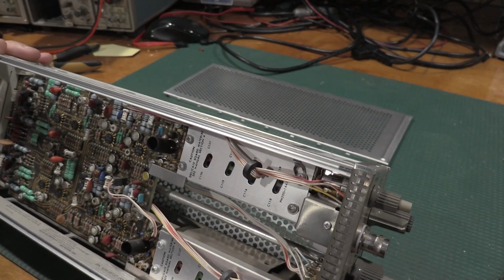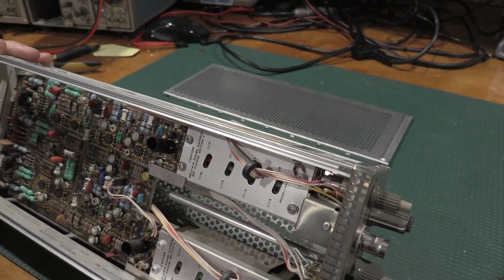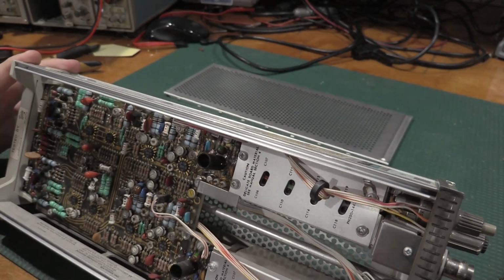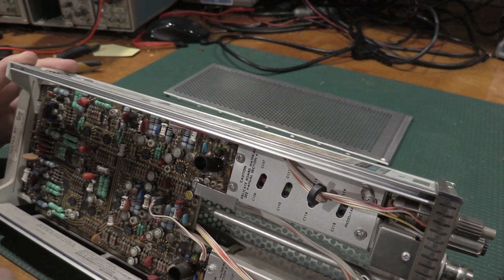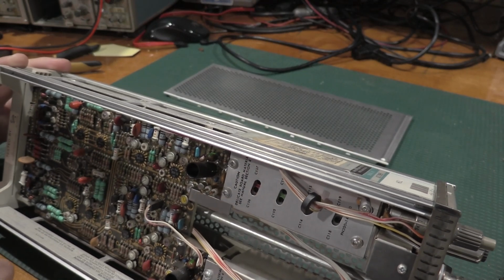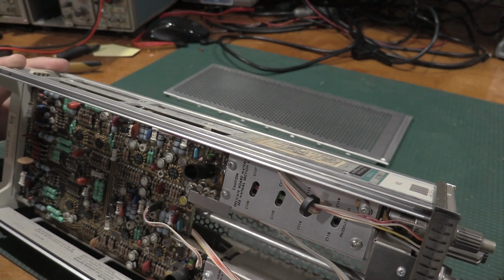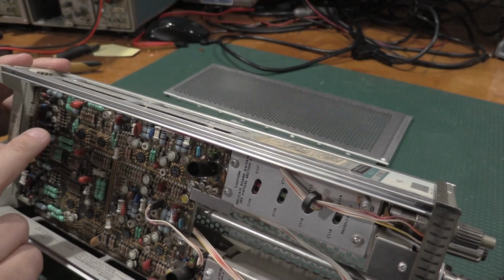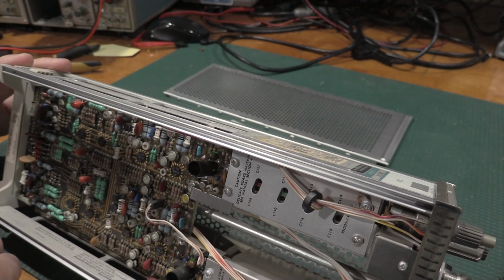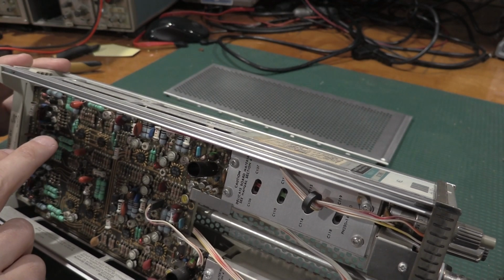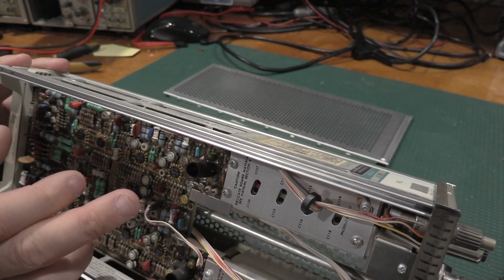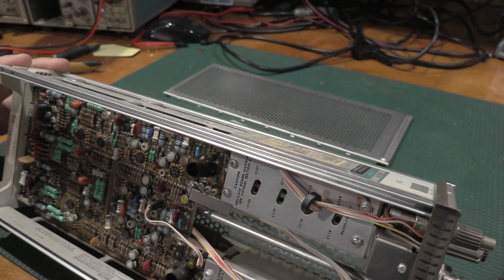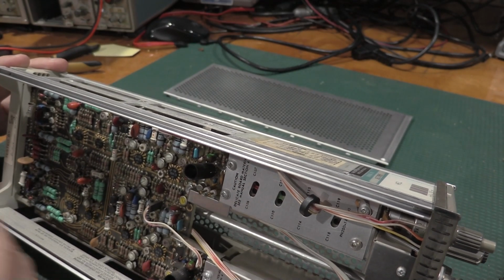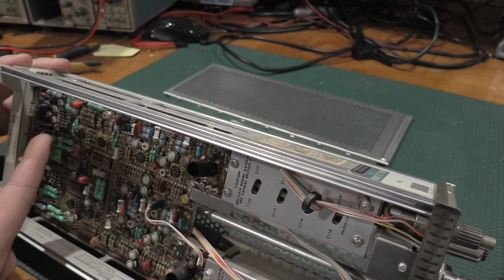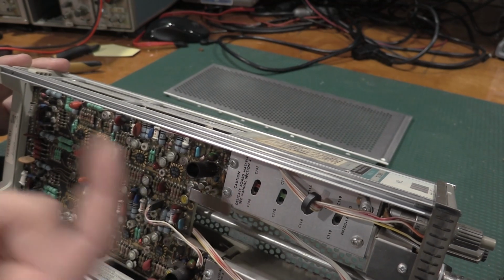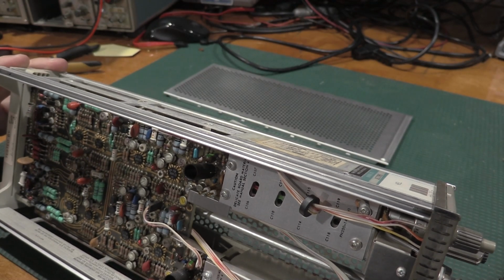One of the reasons for that is it's incredibly difficult to build a variable wide bandwidth amplifier. We have a wide bandwidth amplifier here because we have to go DC to the bandwidth of the scope. But we did a little analog wizardry and we didn't have to make it variable. So we have a front end, but how do we take a measurement? Each one of these ICs is a Tek amplifier IC, and every time the signal goes through it, it gets amplified a little bit. But the total amplification for the channel is fixed. For the sake of argument, we're going to call this a 10x amplification factor. Whatever comes in on this side gets amplified by a set and very accurate 10x and comes out the other end. Well, if that's the case, how can we make a measurement?